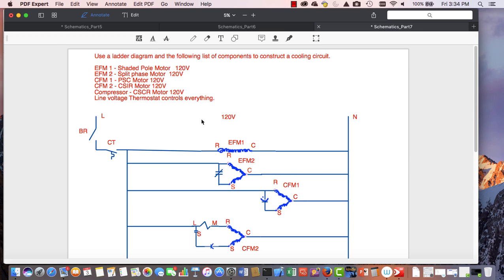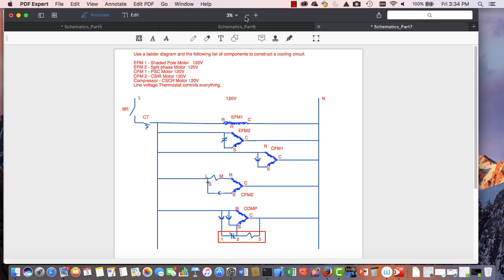Okay, so let's look at our schematic. Let me reduce the size so we can all see it on one page. What we have is a shaded pole motor, a split phase motor, a PSC motor, a capacitor start induction run motor, and my compressor, which is a CSCR motor. They are all controlled by first a breaker and then a cooling thermostat that's a close-on temperature rise. Okay, now here's the sequence of operation. Once the circuit is energized, the cooling thermostat closes, energizes EFM1, EFM2, CFM1 and CFM2, and energizes the compressor. Once the cooling set point has been reached, the cooling thermostat opens and de-energizes all my loads.